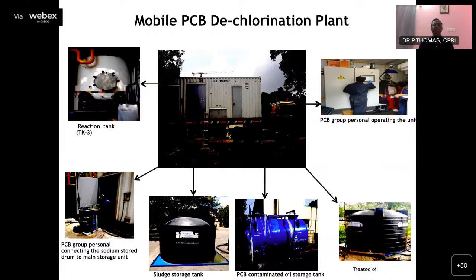We found the oil is sometimes stored in drums, sometimes in transformers, and huge moisture can be present. When moisture is present, the sodium will react with it and create a problem instead of removing the chlorine. It will react with the water and create an explosion. So we have to remove all the moisture. You can literally see the water vapors going out.